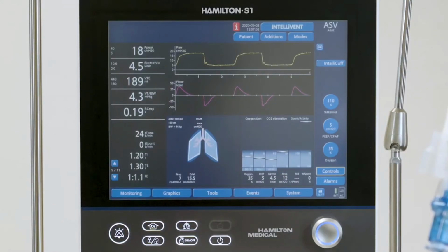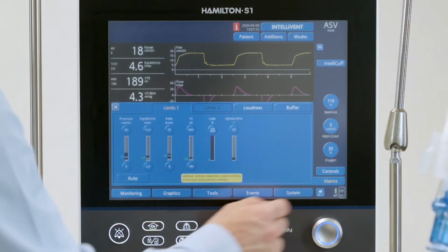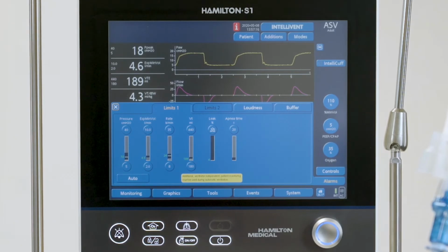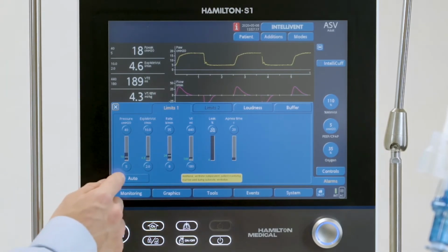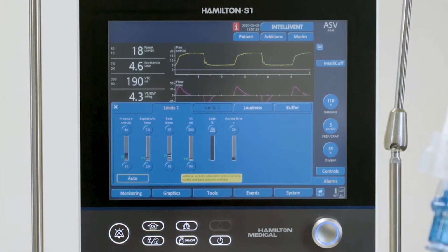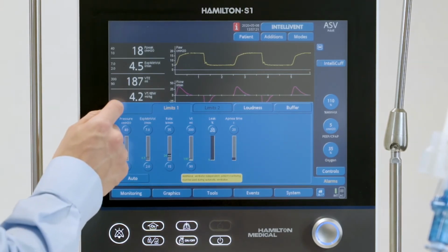After changing the ventilation mode, you should review the alarm settings. To review and adjust the alarms, touch the Alarms button. Then, select the alarm control and adjust it. To set alarm limits quickly, touch the Auto button. All alarm limits, except for the tidal volume and apnea alarms, will be set automatically around the current monitoring parameter values.